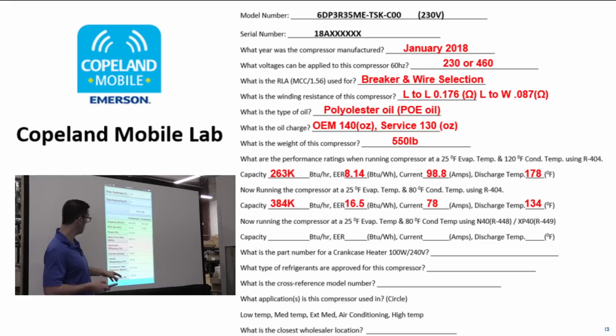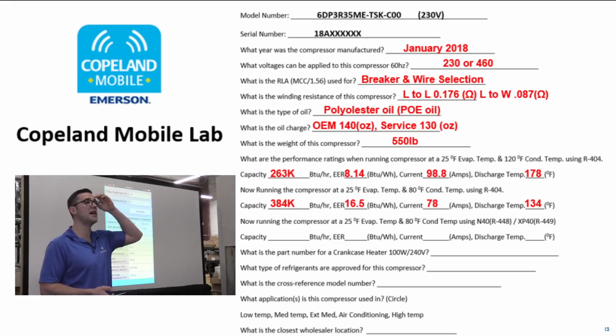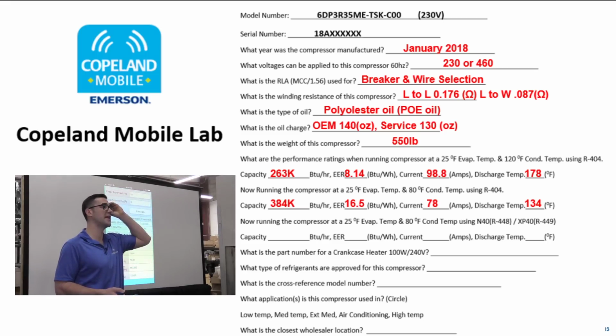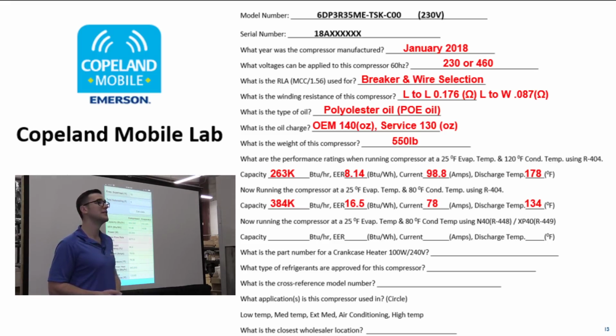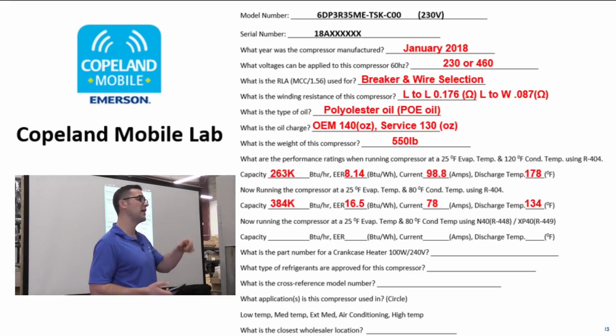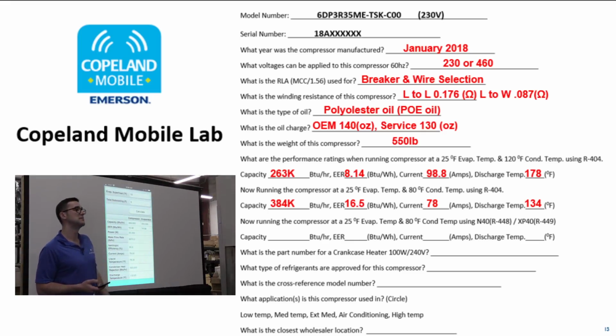Oh, great point. Look at the discharge temperature. It tells you. So you get your temperature probe, you put it on the discharge line. Where does it go in a semi-hermetic? Where do you put your temperature probe? 6 inches away from the compressor. So it should be pretty close to this. How close, plus or minus? I don't know that answer, I'm sorry, but I'll look into that. There will be a plus or minus, but it'll be close to that, because I've tested this.